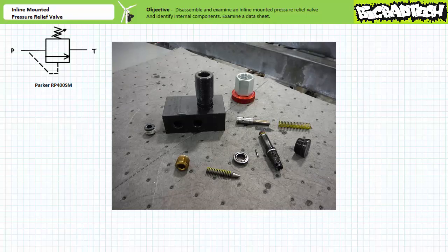Tipping the valve upside down, the dart and screw rattle out. Again, note the dart isn't unusually discolored, silted over, distorted, or covered with any sticky residue or varnish. A visual inspection of both the pilot and primary sections similarly indicate that the passageways are clear of contaminants. The pilot section is essentially cleared.